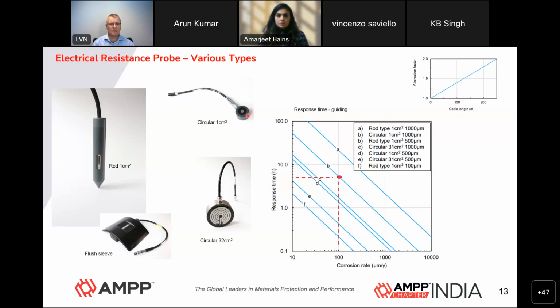So if you can start working on that, because that's a huge problem today in countries like India, where the distribution transformers' earthing is extremely close to the pipeline. It may not be a problem in the western part of the world, but in countries like India and Bangladesh, where the right of way is restricted, we are sharing common corridors with these 11 kV, 33 kV networks.